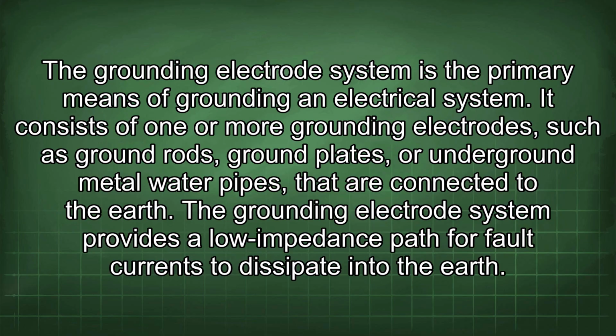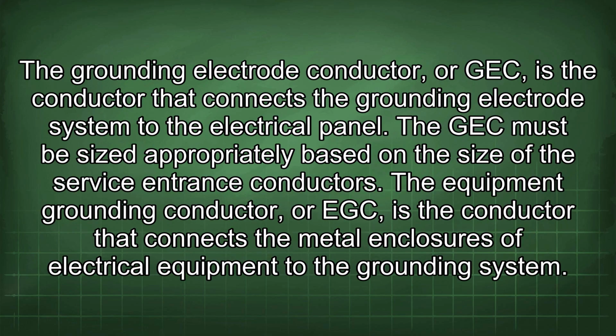The grounding electrode system is the primary means of grounding an electrical system. It consists of one or more grounding electrodes, such as ground rods, ground plates, or underground metal water pipes, that are connected to the earth. The grounding electrode system provides a low impedance path for fault currents to dissipate into the earth. The grounding electrode conductor, or GEC, is the conductor that connects the grounding electrode system to the electrical panel. The GEC must be sized appropriately based on the size of the service entrance conductors.